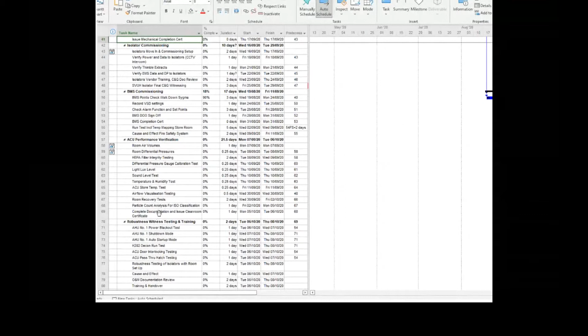This part of the performance verification, the nuts and bolts of it, is you need to get a certificate at the end of the day saying the room is performing in terms of particle counting. For the compounding room, the allowance at 0.5 microns was 3,520 particles, and here are the actual results: 55, 96, 55, 39, etc. So the performance was very, very good.